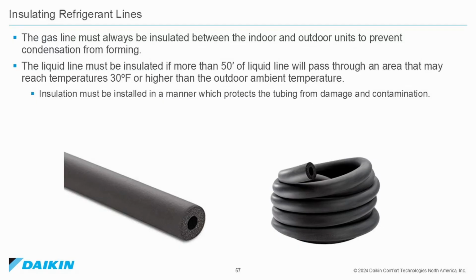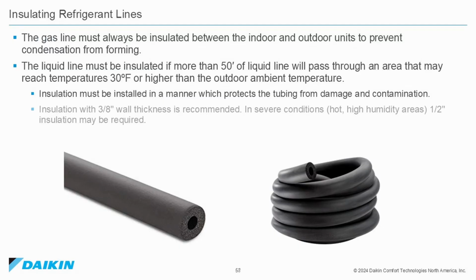Insulation must be installed in a manner which protects the tubing from damage and contamination. Insulation with 3/8 inch wall thickness is recommended. In severe conditions, hot, high humidity areas, 1/2 inch insulation may be required.